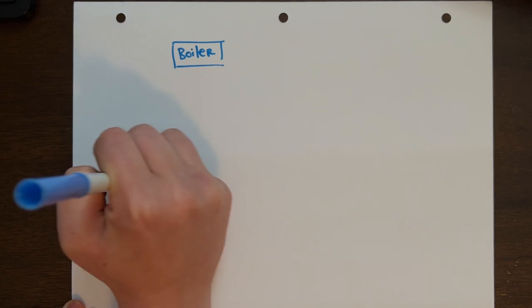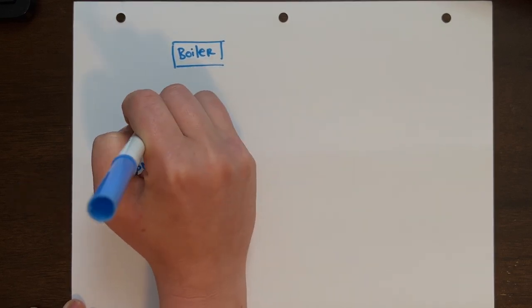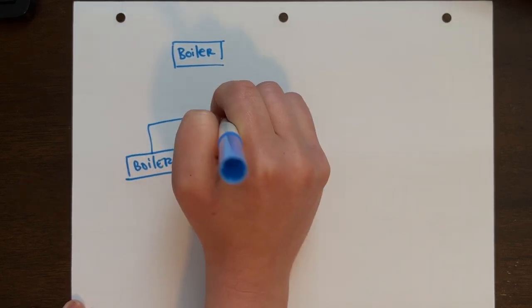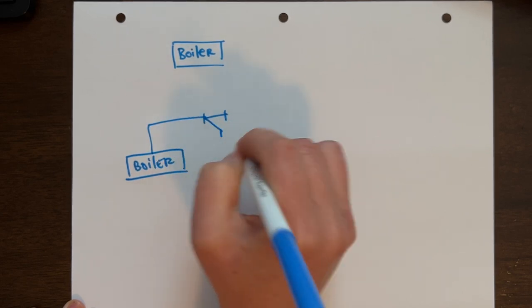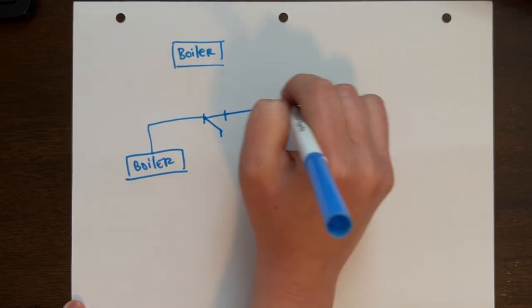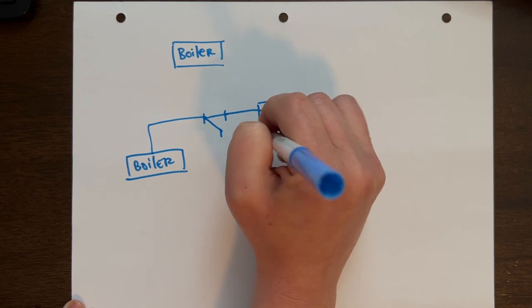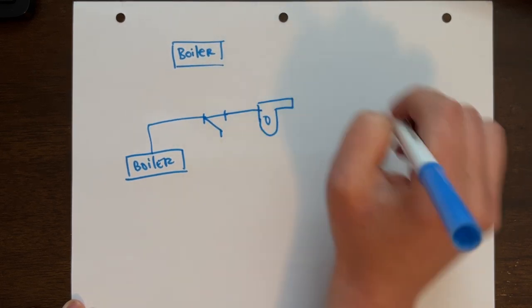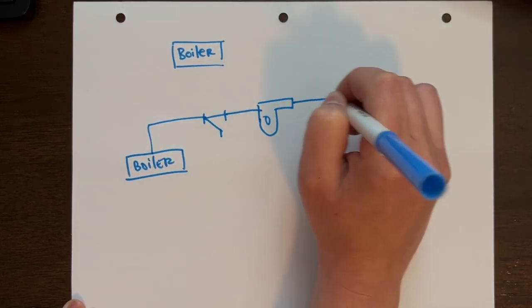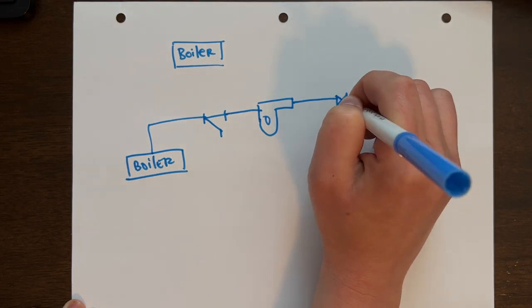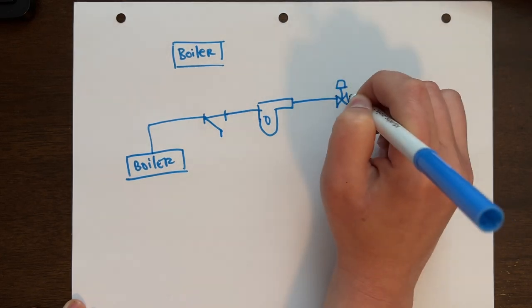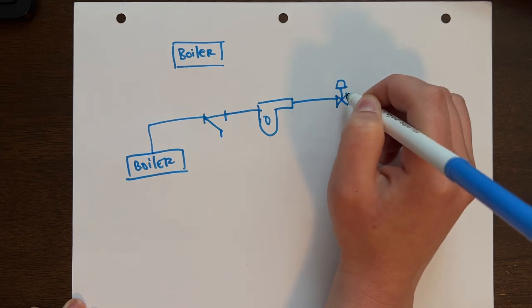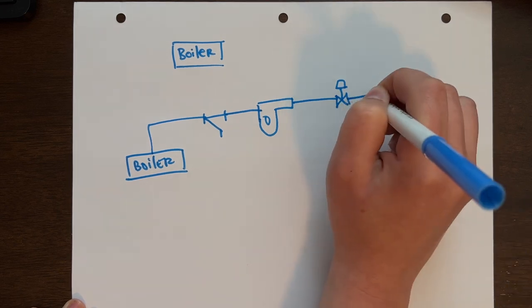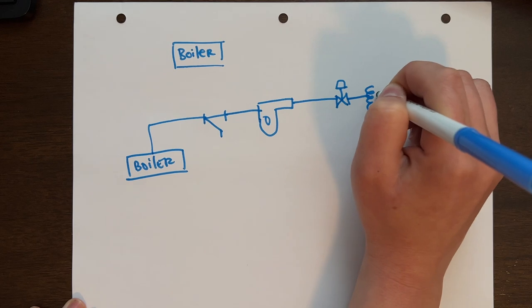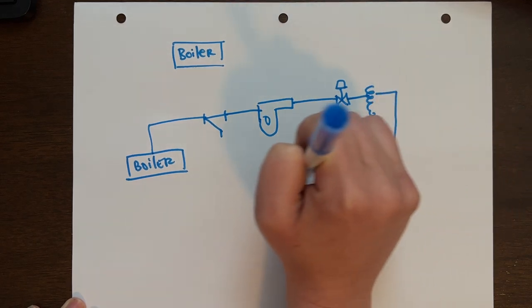that you will design. That boiler will supply water, take it through a strainer. This keeps your system clean before it hits your pump, because your pump is a very important piece of equipment that keeps water flowing throughout your system. It'll then go somewhere to a control valve, which controls the flow at the individual coils. It'll go through a coil, and it'll go all the way back to your boiler.